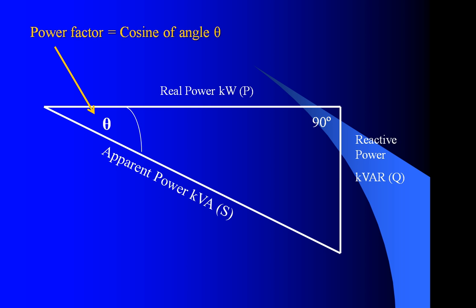If we look at the resulting power triangle, we find an important part — the power factor — which is the cosine of this angle. The power factor can also be shown as the cosine of the angle, the real power over the apparent power, P over S, which is sometimes seen as kilowatts over kVA, or in circuits R over Z.